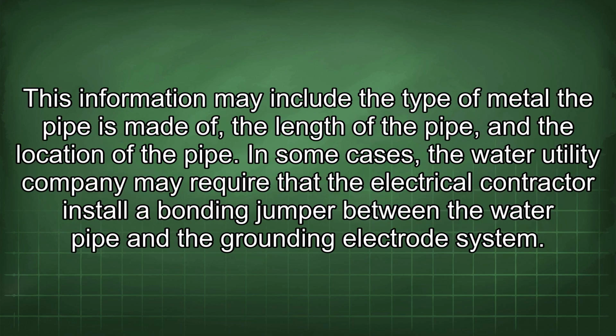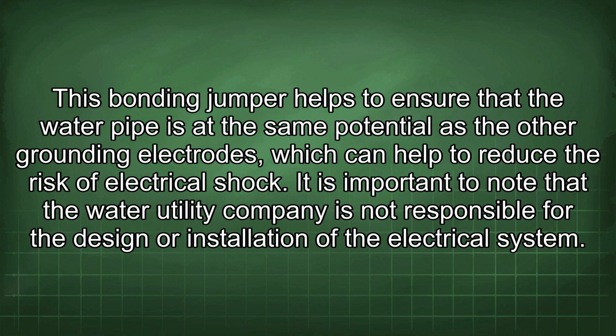This information may include the type of metal the pipe is made of, the length of the pipe, and the location of the pipe. In some cases, the water utility company may require that the electrical contractor install a bonding jumper between the water pipe and the grounding electrode system. This bonding jumper helps to ensure that the water pipe is at the same potential as the other grounding electrodes, which can help to reduce the risk of electrical shock.